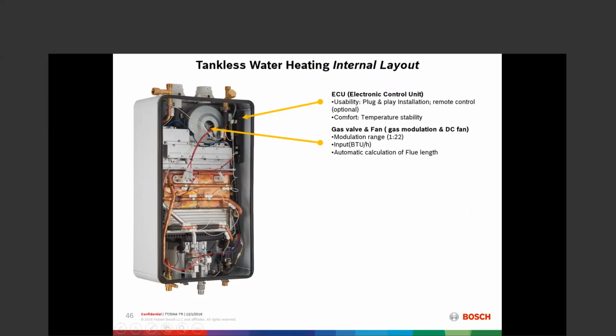Since 2004, all of the high output Bosch tankless water heaters have used negative pressure gas valves. In this configuration, we've returned to a positive pressure gas valve. And we did that in order to allow the ECU, via the OptiFlow software, to independently adjust the gas flow from the airflow. And again, that's so that we can constantly tweak and make sure that the unit is hitting the highest possible combustion efficiency.